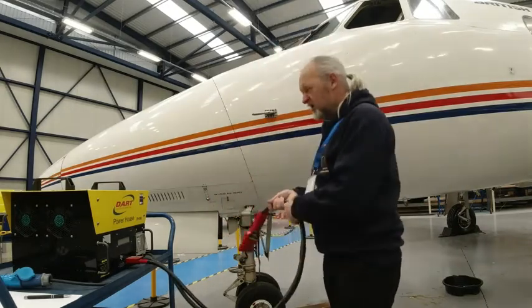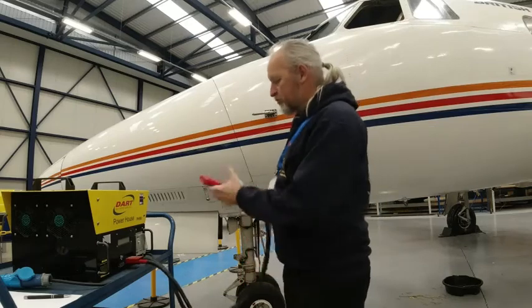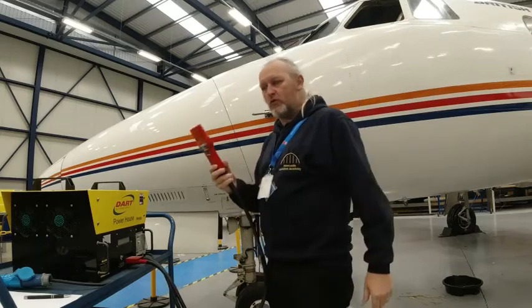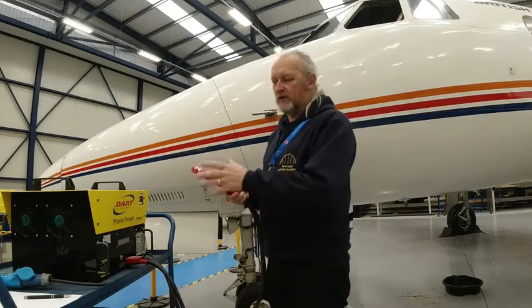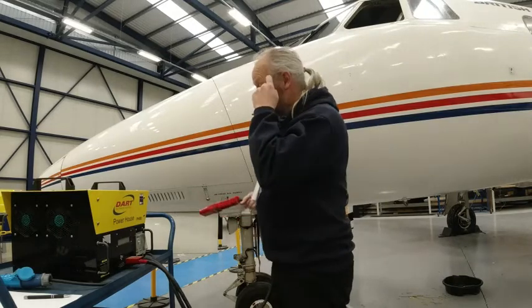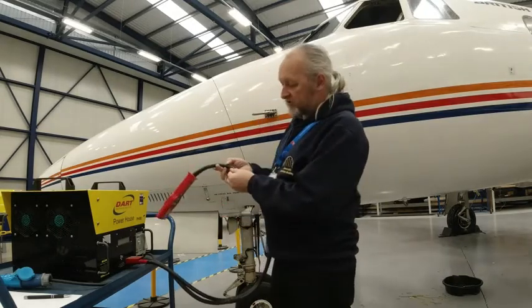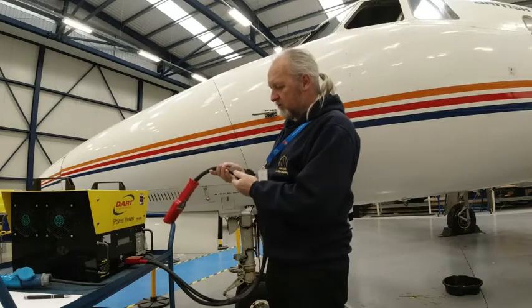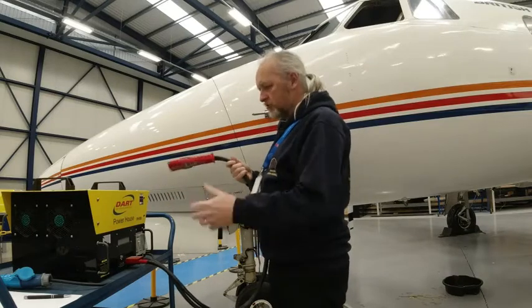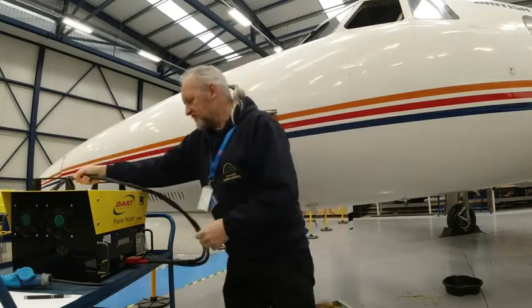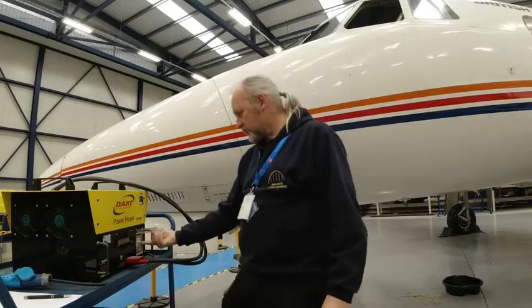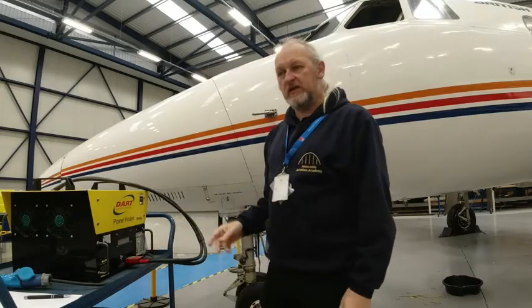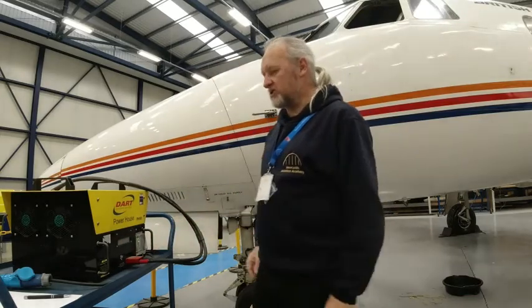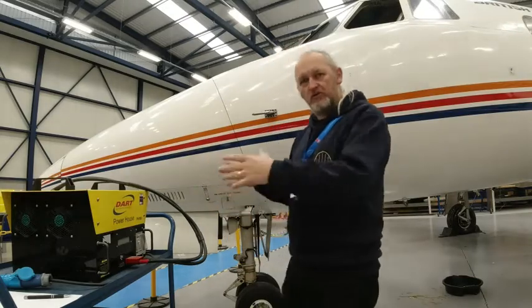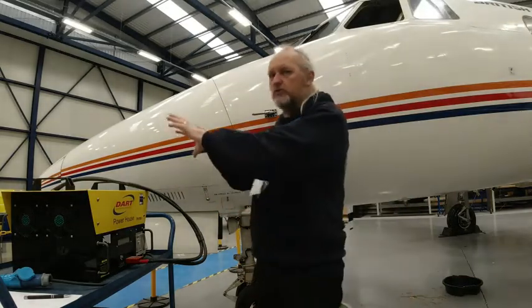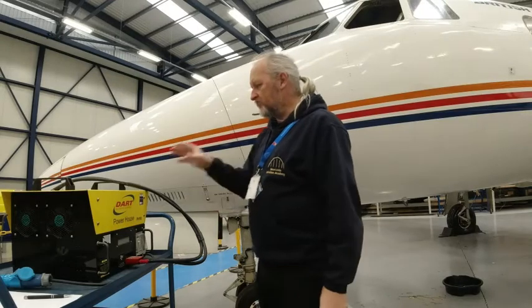We're looking to see if it's wet, covered in water or hydraulic fluid or anything - if so you might want to clean that off. Any nicks or conductors showing, any copper showing through, don't use it. On the set itself, make sure the switches work, they're accessible, all there, and it looks like it's actually in use and not broken. There should be no signs saying don't use this power set, and it should be the right one for the job.